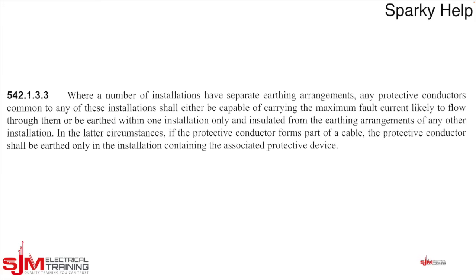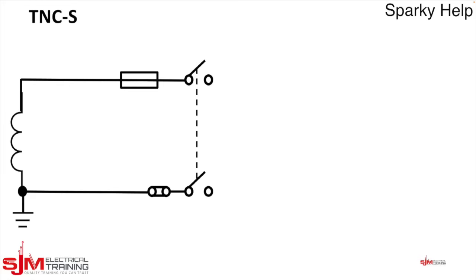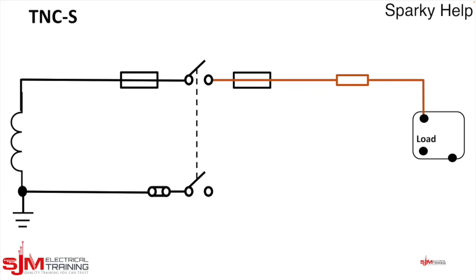Otherwise, what it says on here is you can be insulated from the earthing arrangements of the installation where it comes from. And it's that one that we're going to concentrate on now in the latter circumstances. So if you're going to isolate from the original earthing system, the protective conductor forms part of the cable. The protective conductor shall be earthed only in installation containing the associated protective device. What does that look like? Well, here's our TN-C-S, and as always, draw it as a single phase because it's just easier. We're going to put the line conductor in. I'm not going to any specific load of any description, so it could be a socket, could be an entire building. I'm not showing the protection, I'm just showing the point of connection where it goes in. And we're going to put our neutral in, and we're connected to a TN-C-S.